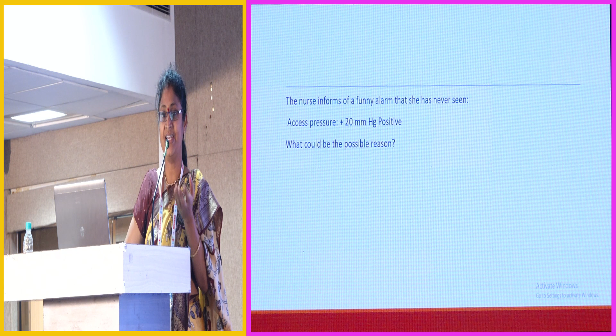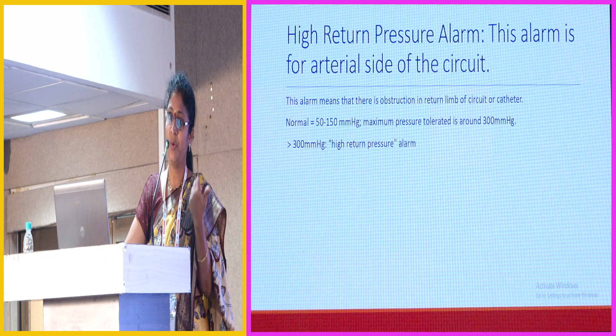Then second, the high return pressure alarms. As already discussed, the usual pressure is 50 to 150. You will get an alarm only if the return pressure is more than 300. If the return pressure is high, check the arterial side of the catheter or the filter. Next is the high filter pressure. As I told you, it can be either a gradual rise or a sudden rise. It indicates a dying filter. Filter pressure tells you the filter's life. Blindly you can remember it like that.